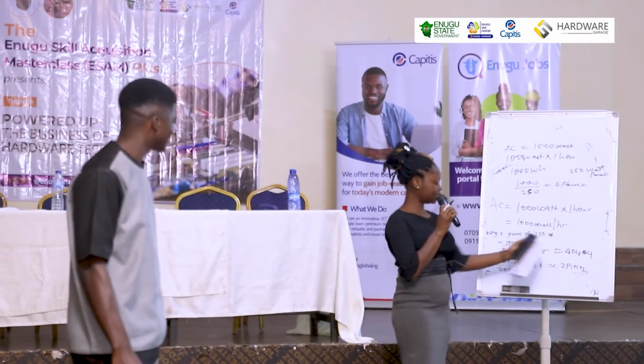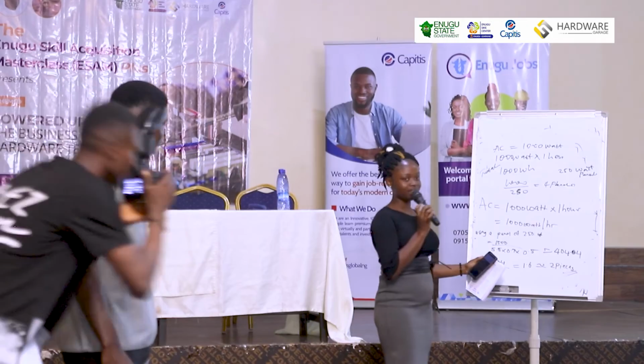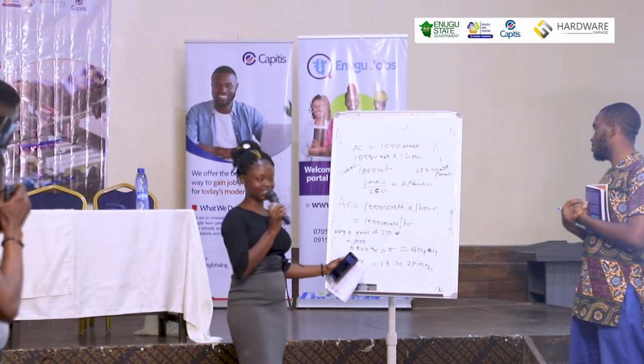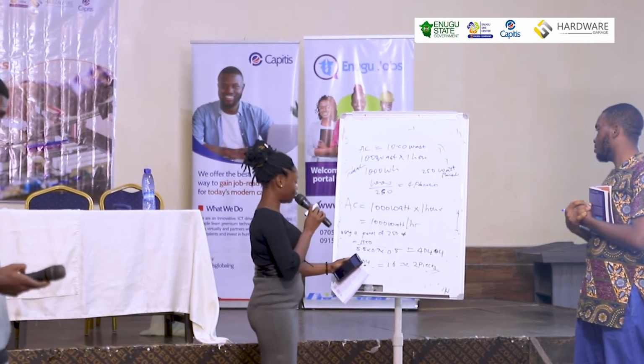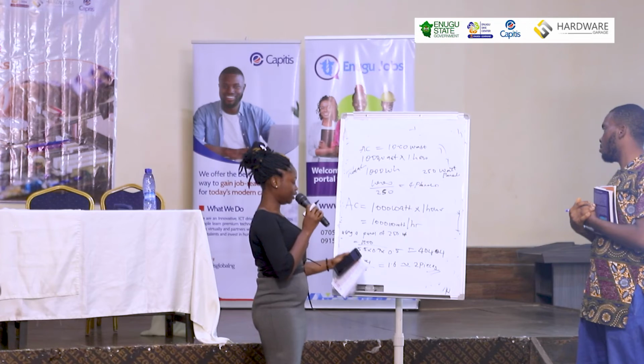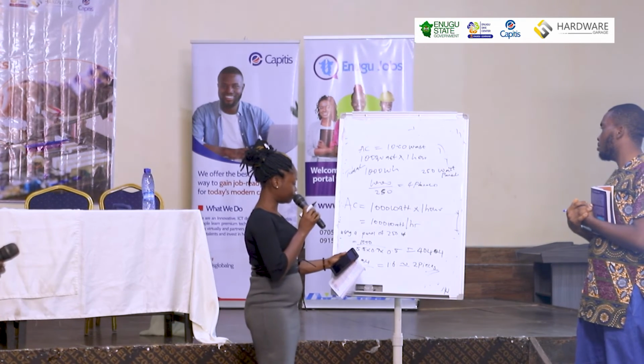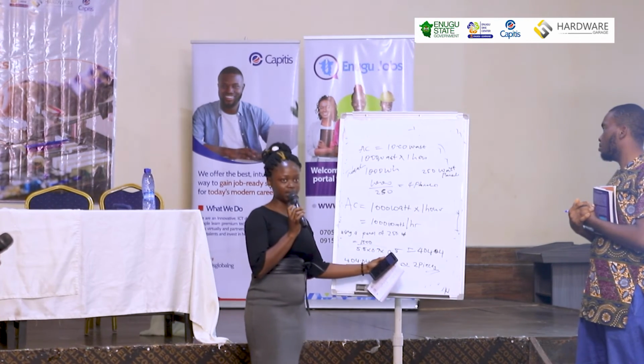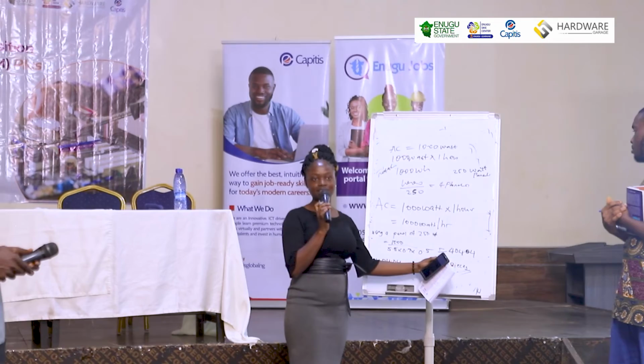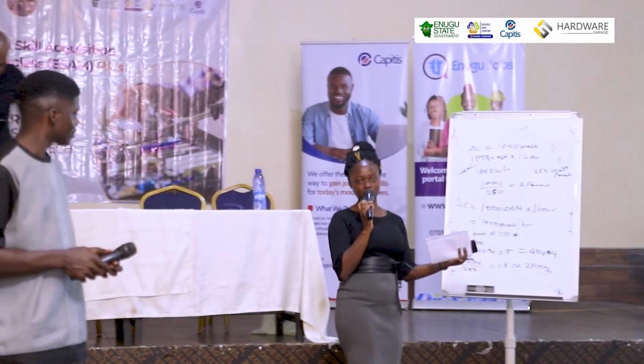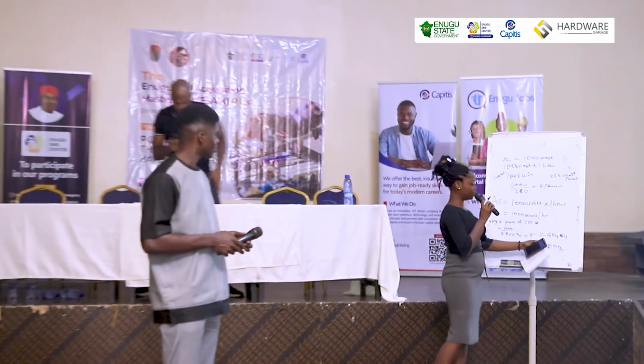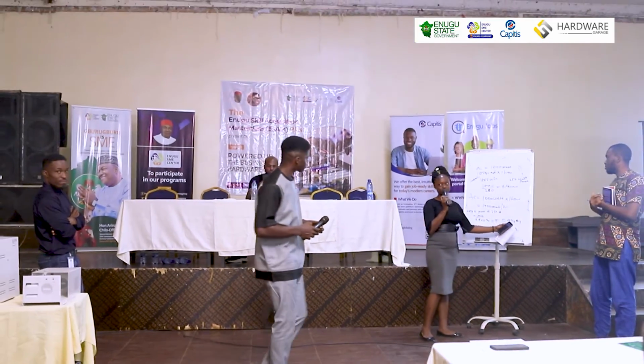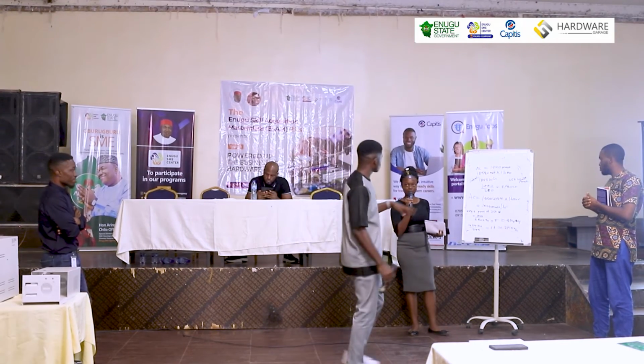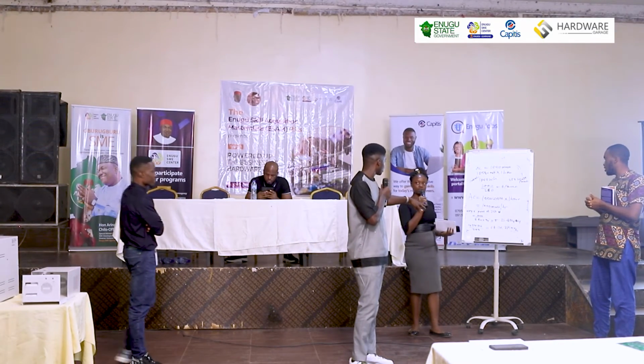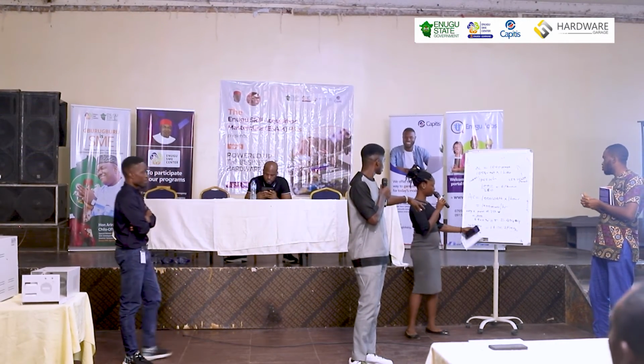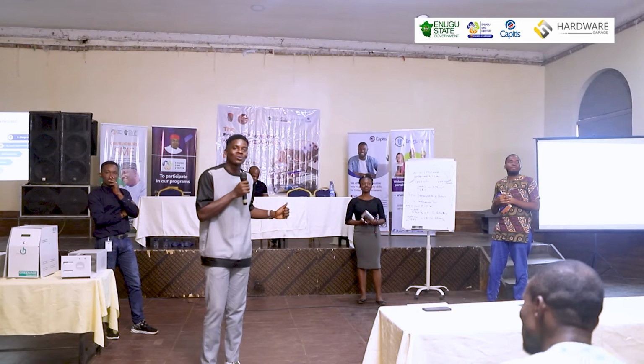So after we've gotten that answer, we divide by the solar panel size that is in the market, as you said, so we're using the one of 250. When we divide that with 404, we get 1.6. Since the panel has to be in whole numbers, we approximate to the nearest whole number, which is 2, and that's 2 pieces of 250 watts panel. So she's correct.